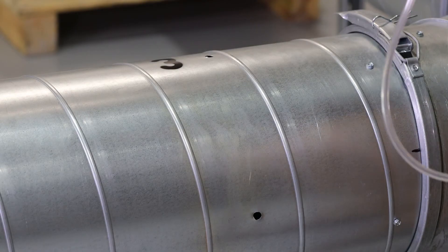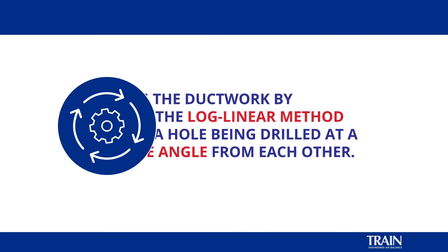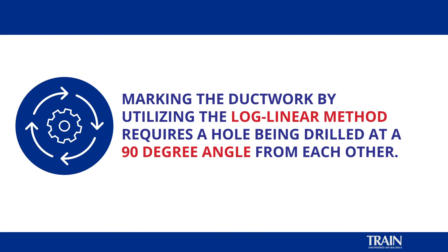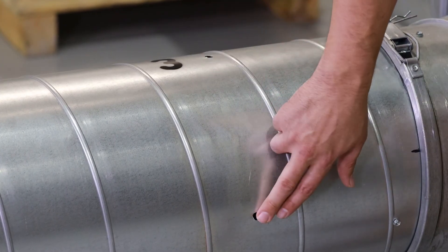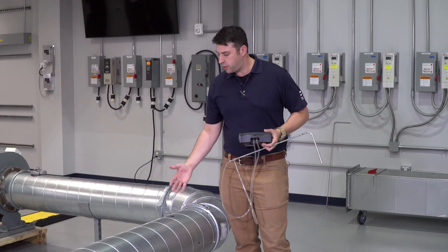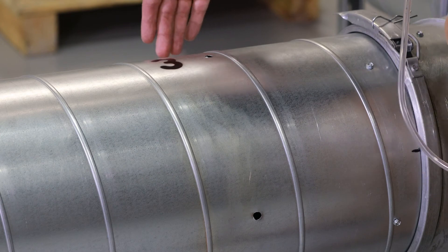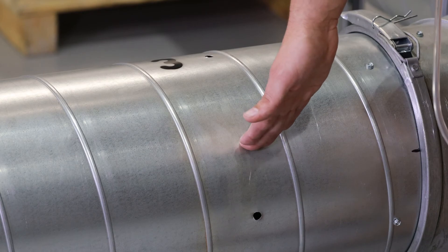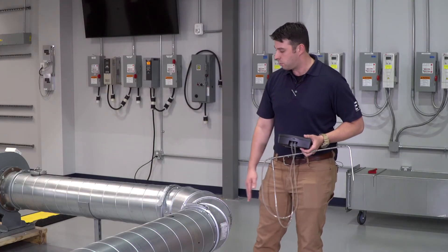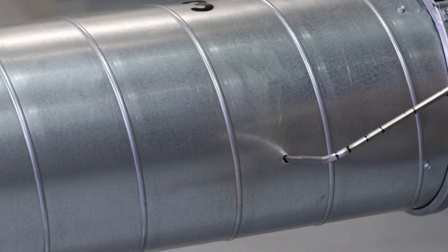For our next demonstration, we are going to perform our pitot tube traverse of our round ductwork. Marking the ductwork utilizing the log linear method requires a hole to be drilled at 90 degrees from each other. In this instance, we have drilled a hole at the top of the ductwork and on the side of the ductwork. Technicians in the field might find that the holes need to be drilled in a different location, such as two positions at the top. For this purpose, we will go ahead and use the top and the side, making sure that the pitot tube is properly oriented.